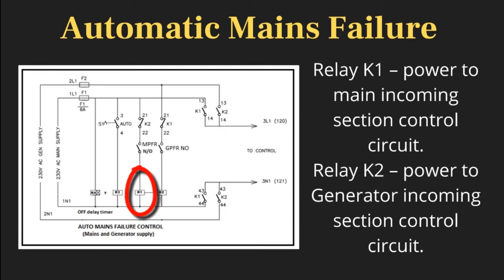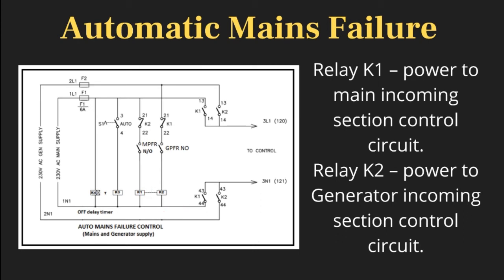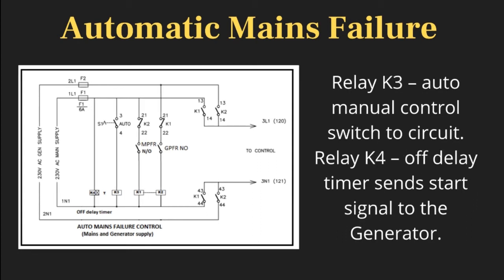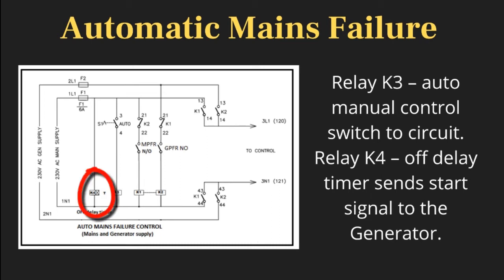Relay K1 provides power to the main incoming section control circuit. Relay K2 provides power to the generator incoming section control circuit. Relay K3 is the auto-manual control switch circuit. Relay K4 is an off-delay timer that sends a start signal to the generator.